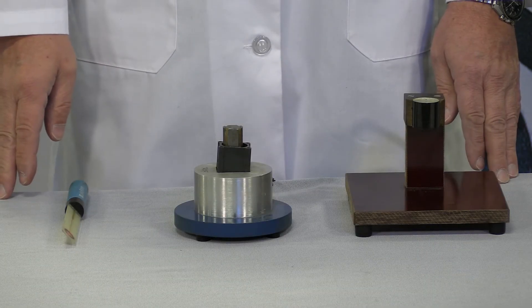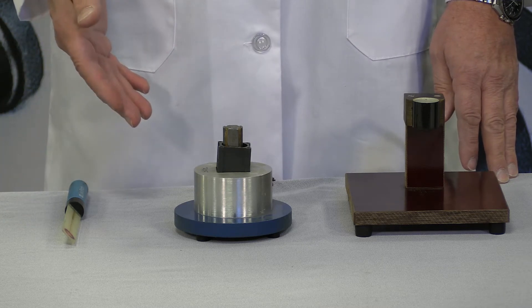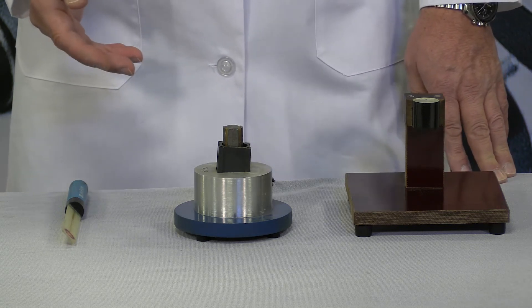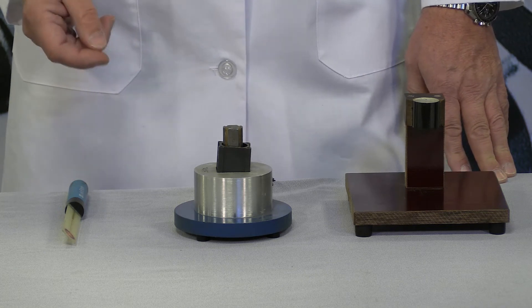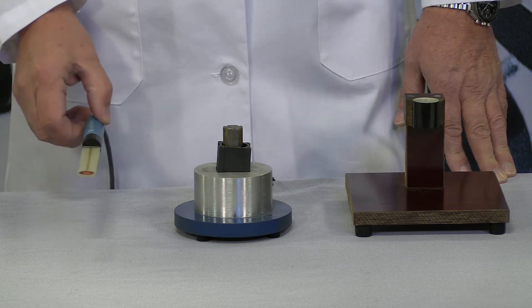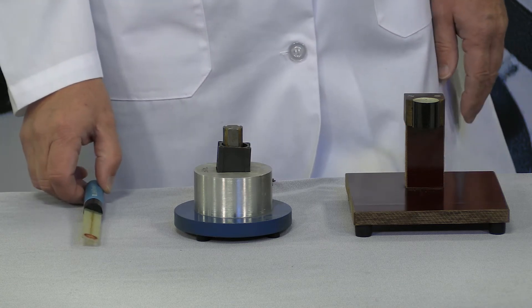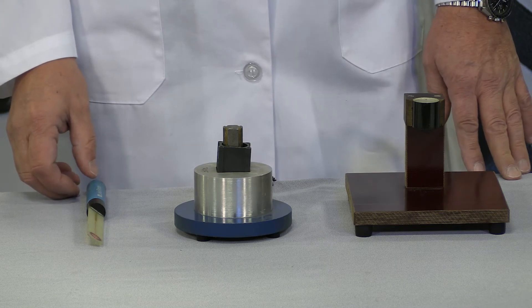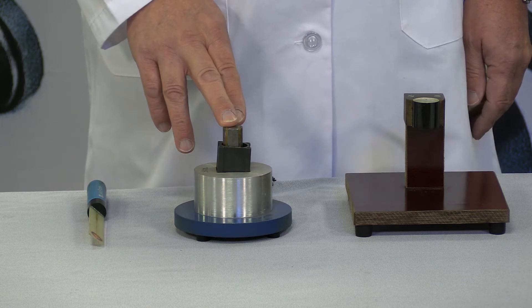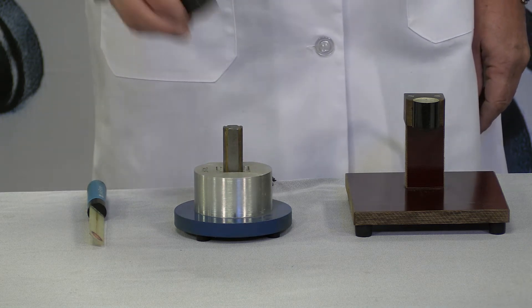The devices which connect to these flux meters are called search coils and Helmholtz coils. Search coils are custom-made fixtures with a large number of copper windings shaped to provide an electric current when a magnet or set of magnets are pulled out of the plane of the coil. They can be a simple transverse coil on a flat holder that can be inserted into a gap between magnets to measure the flux between them, or they can be shaped to encompass the entire magnetic structure of a motor housing, where you can obtain a flux for the entire system instead of a single magnet.